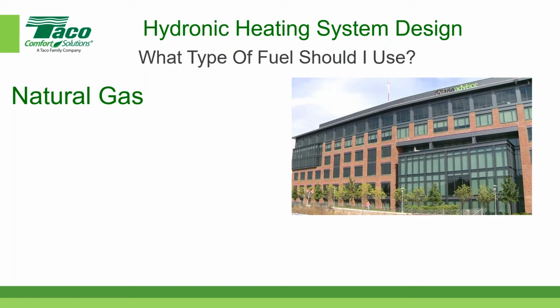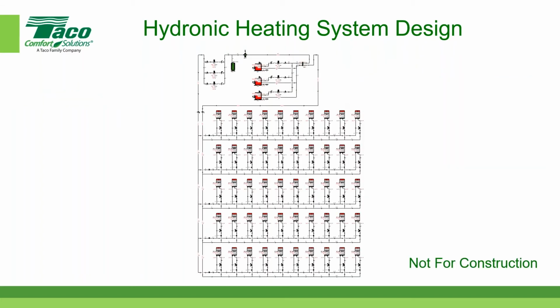Now, the first diagram I'm going to show you is almost impossible to read, but this is a hydronic heating system, complete design. We have 10 terminal devices per floor. We have 5 floors, you can see. So we have a total of 50 terminal devices. We have 3 boilers and pumps. And now I'm going to zoom in on the next slide so we can look at each of the components to see how they're arranged and what order they happen to be in. But I wanted to show you a picture of the overall system first.